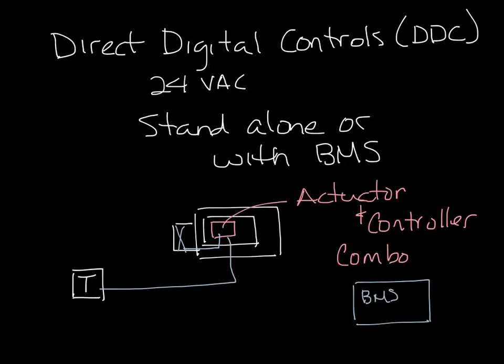The difference here from Analog is that there's a building management system somewhere, so there's a computer running software that is connected to this VAV box controller, and also to multiple VAV boxes so that you can see your entire system sitting in an office somewhere, or maybe off-site. DDC controls are the most common controls we see today.